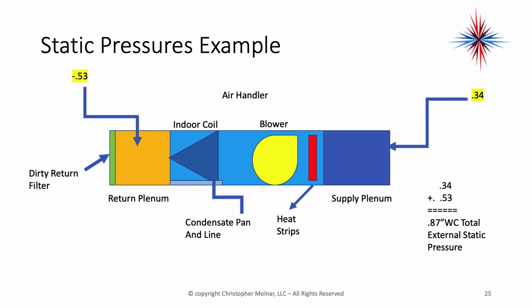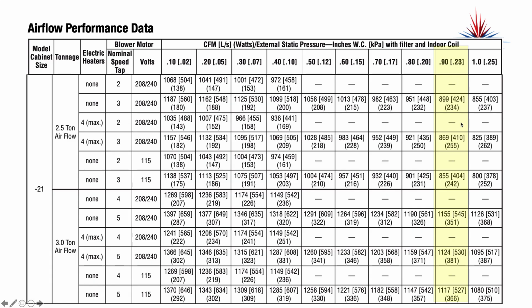Here's another example. Negative 0.53 and a 0.34. Add them together, I'm going to come up with a 0.87 inch water column total external static pressure. So all of a sudden I go over to my airflow performance. A 0.9, okay, which is what that will round to, is much too low for a 2.5 ton system, and it's too low for nominal for a 3-ton system.